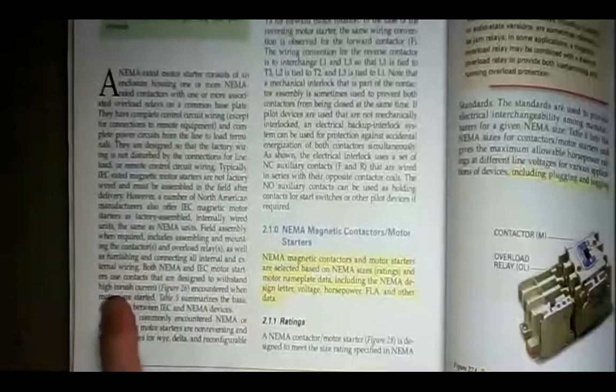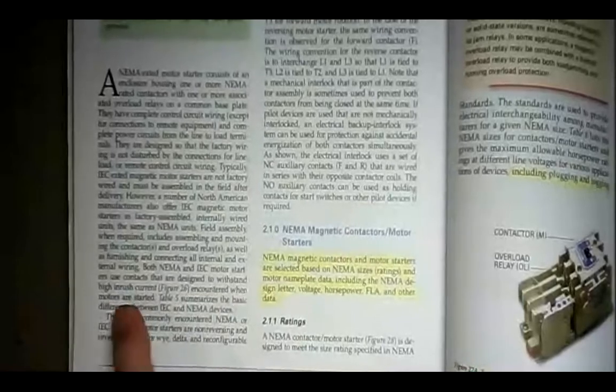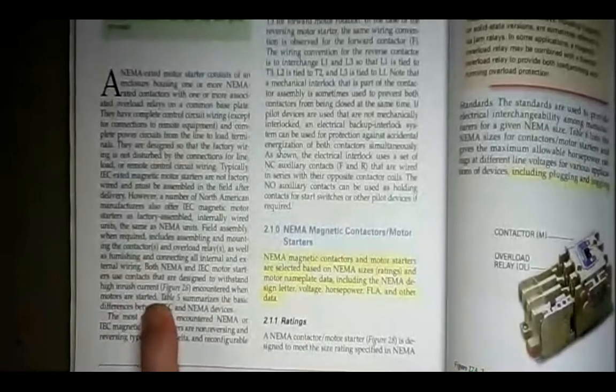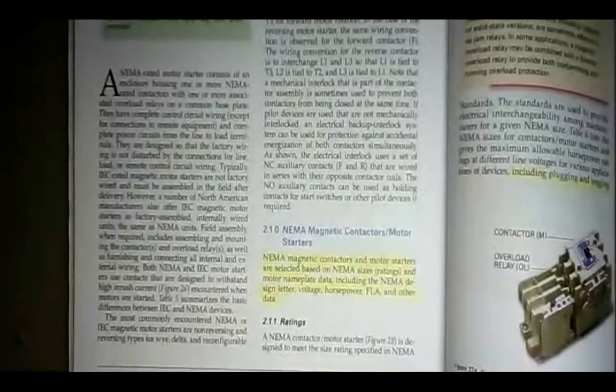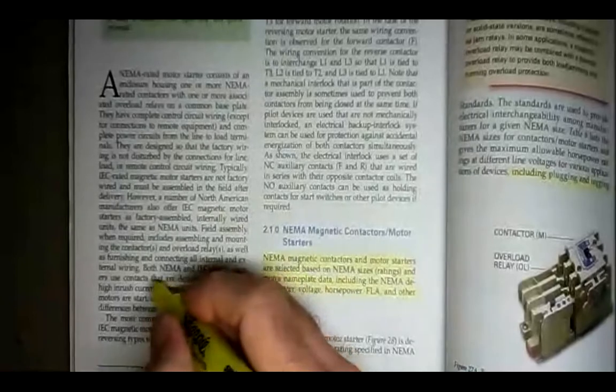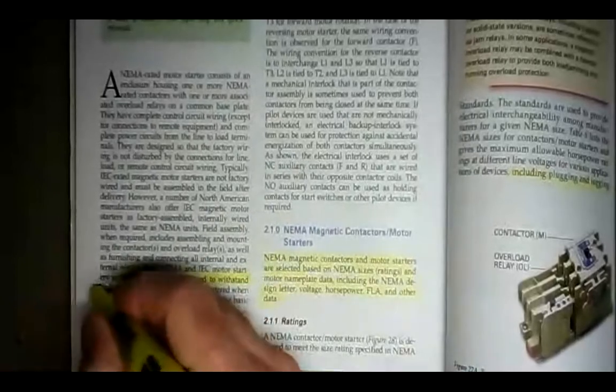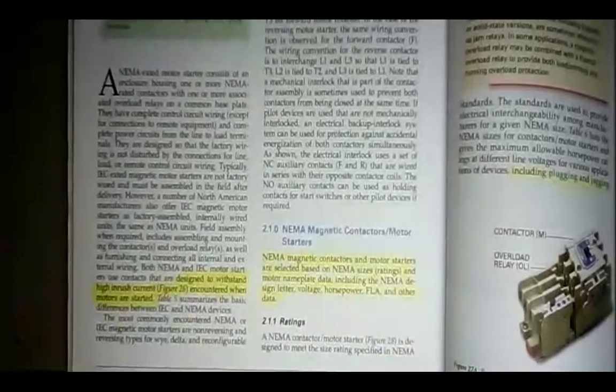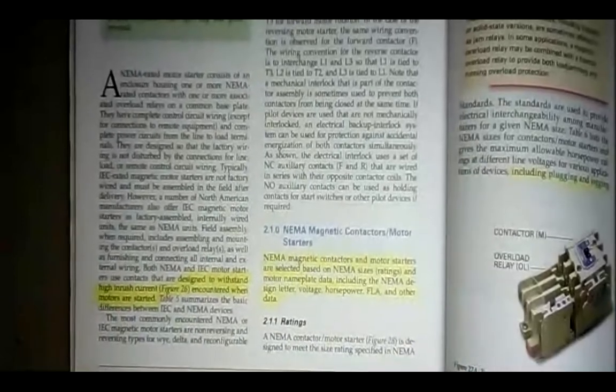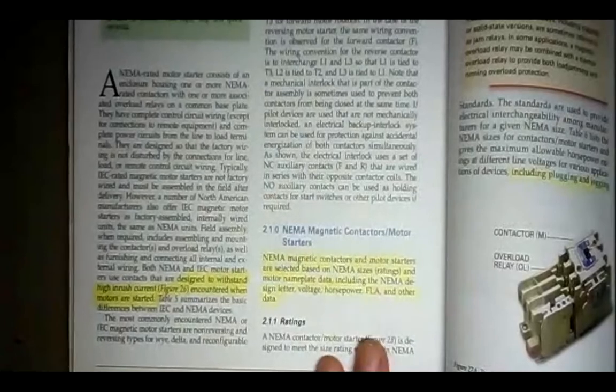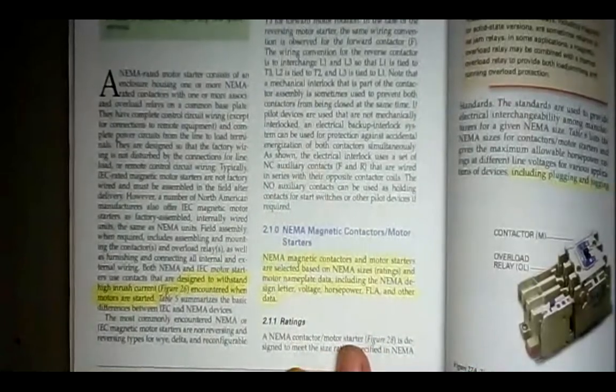Both NEMA and IEC motor starters use contacts that are designed to withstand high inrush currents encountered when motors are started. They weren't telling us the 6 to 8 times. I think that's under motors. This is motor controls, but in the section on motors, I think we learned that the starting current of a squirrel cage motor can be 6 to 8 times. Yeah, I did cover that one in the last chapter.